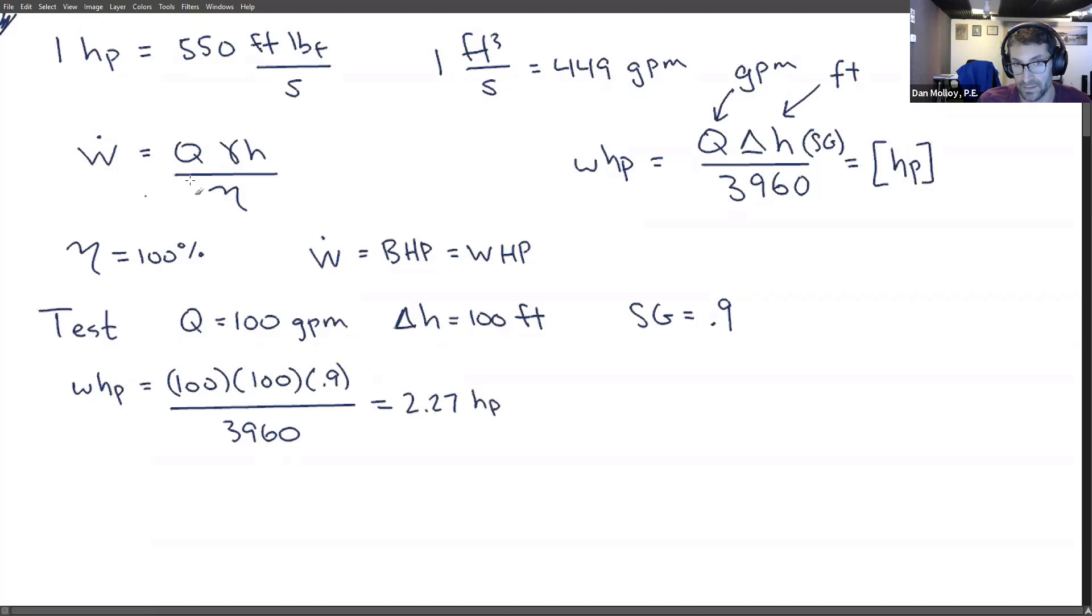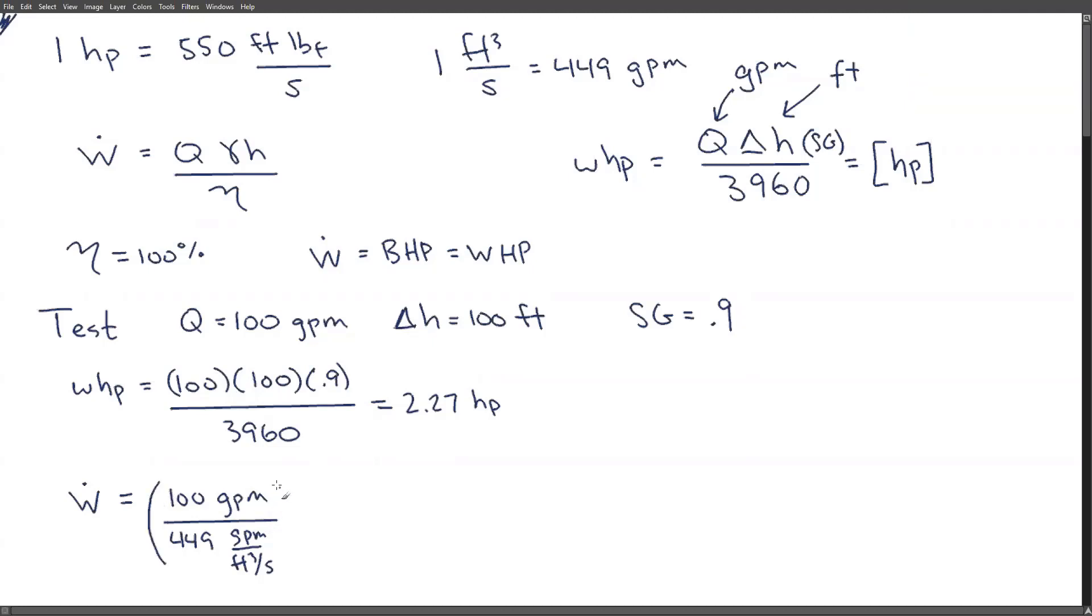And now let's check that against this equation. So we're saying the work developed by the pump should be the same as the hydraulic horsepower for 100% efficiency. But now we've got to do a whole bunch of unit conversions. So let's have some fun. We're going to start with 100 GPM and then divide by 449 GPM per cubic foot per second. And then we're multiplying by the gamma. Let's talk about gamma for a moment. What is the definition of specific gravity?